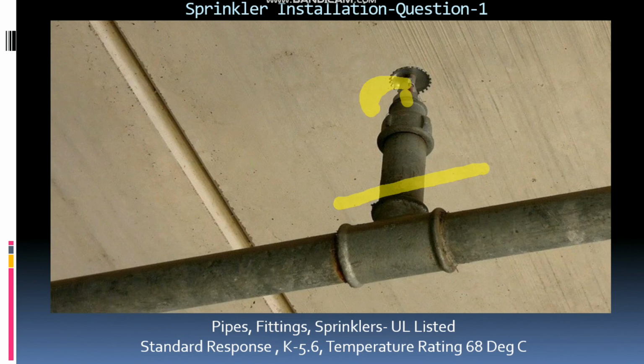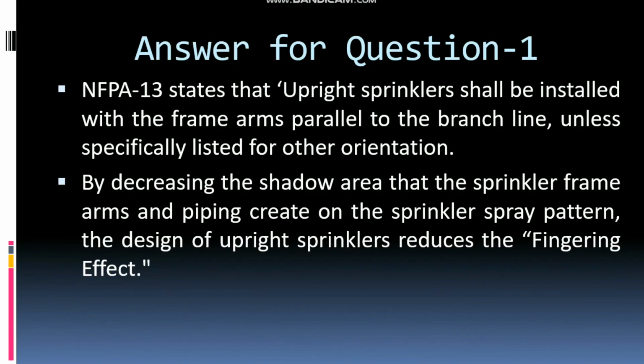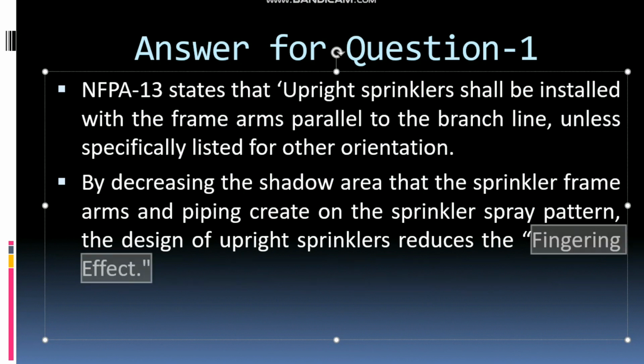That is the approved one, and UL cannot do anything about this type of mistake which happens on the site. As I mentioned here, NFPA 13 states that upright sprinklers shall be installed with the frame arms parallel to the branch line unless specially listed for another orientation. Why are we doing it like this? We want to avoid the fingering effect. That means we need to decrease the shadow area that the sprinkler frame arms and the piping create in the sprinkler spray pattern. That is the reason this installation is very important.